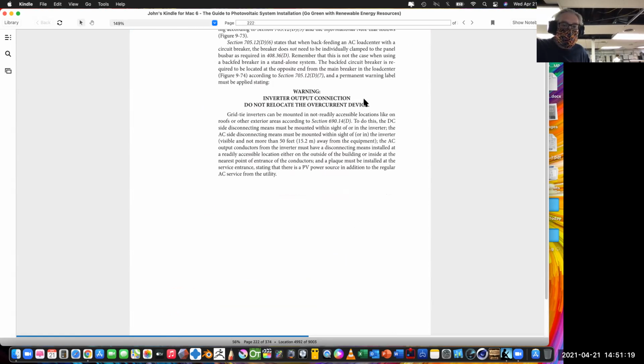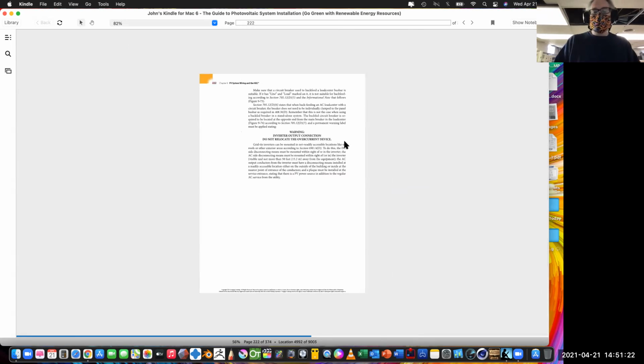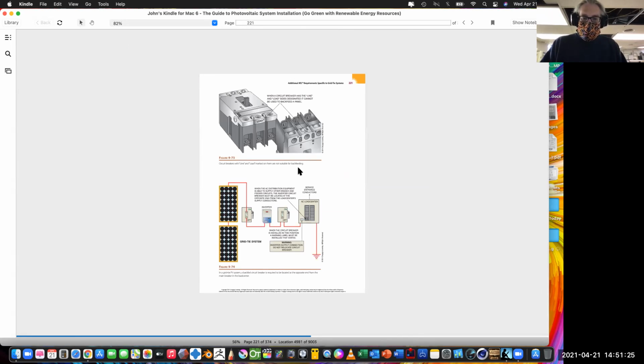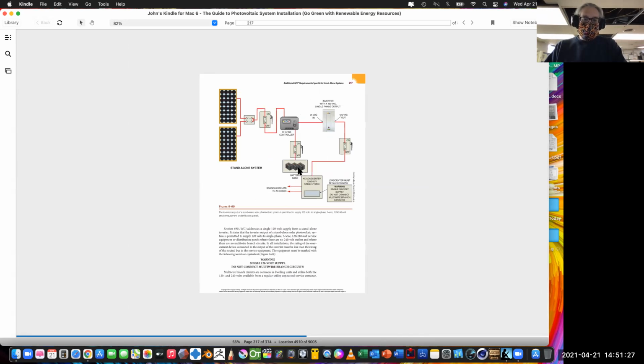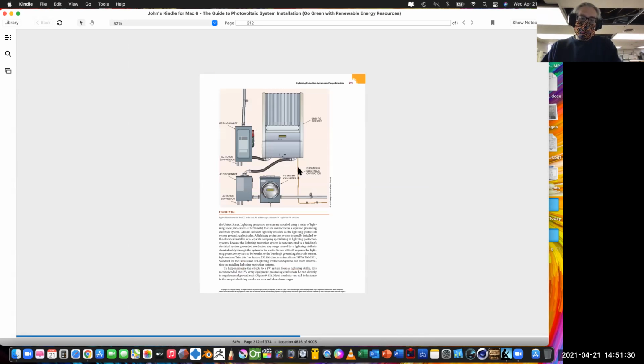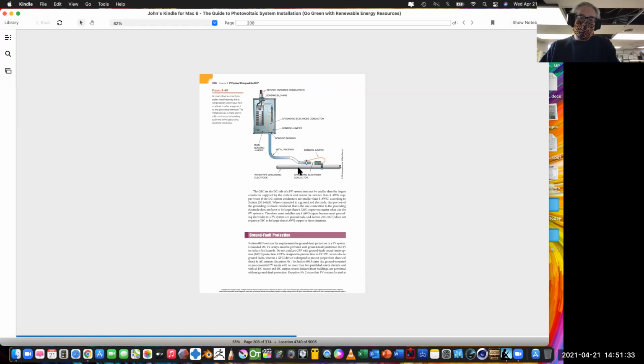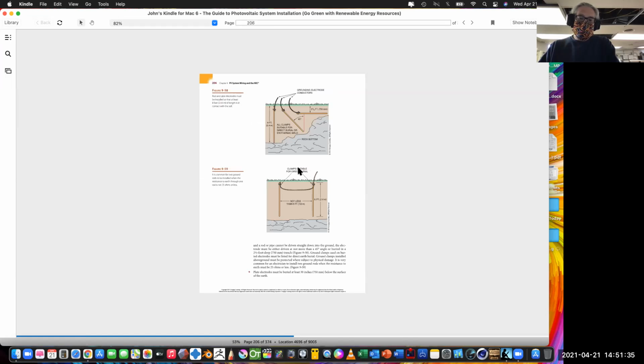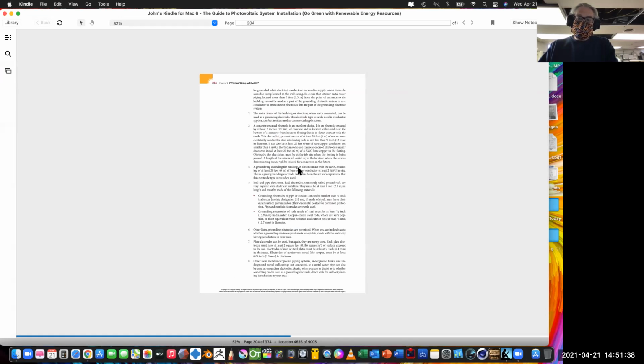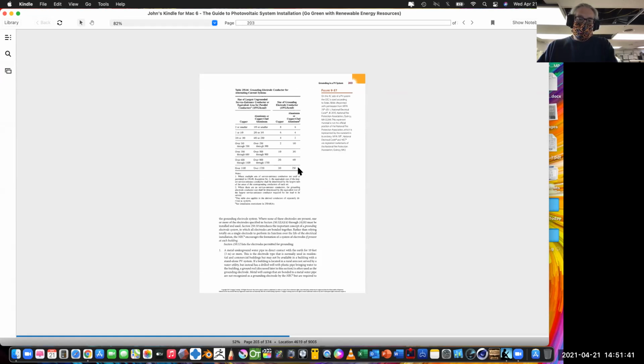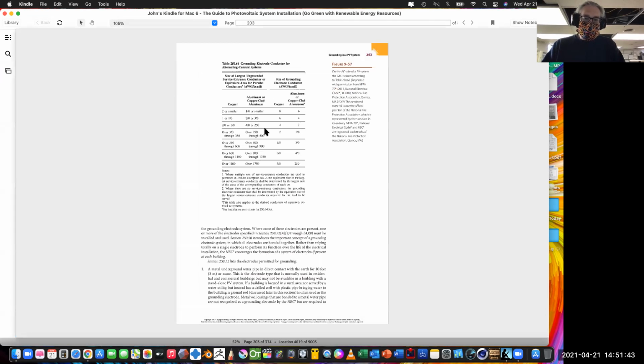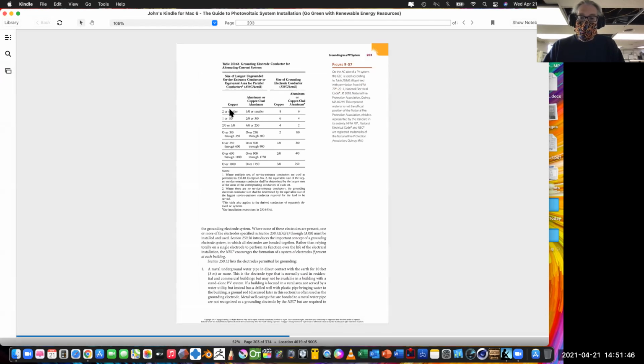And then we have our final, so that's chapter 9. I was hoping that on the last part of this you got a better idea of what you really need to do and how you need to wire this up and what is most important. There is a lot of code in here, but it's overdone, especially on grounding, way overdone. All we're needing to do is make sure we understand how to size our actual conductor wire, our equipment grounding conductor, the green one, and it's going to match or be bigger than our main power conductors, like our number 6, which we talked about.